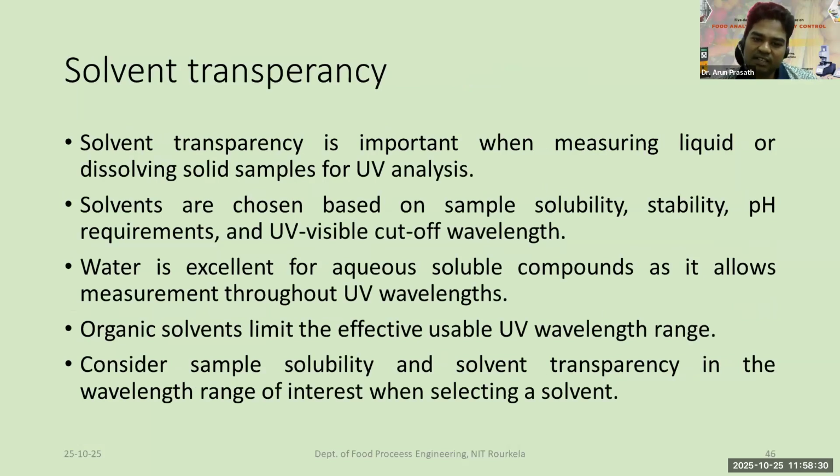Solvent transparency is very important when you are measuring liquids or dissolving solid samples for UV analysis. The solvents are chosen based on the sample solubility, stability of the solvent, pH requirement, and the UV visible cutoff wavelength. These are the essential things to be addressed before selecting a particular solvent. And moreover, the solvent should have least absorbance.